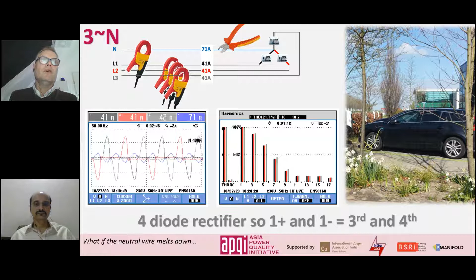Here you see the third harmonic has vanished. That's because the neutral wire has been cut or melted down. And now you see the 5th and the 7th harmonic coming up, and the line current has dropped a bit from 41 amps to 35 amps. But the chargers are still working and still delivering 3.5 kilowatts.